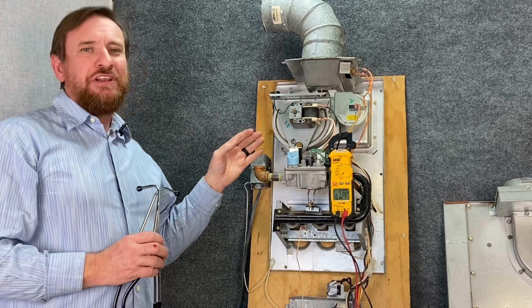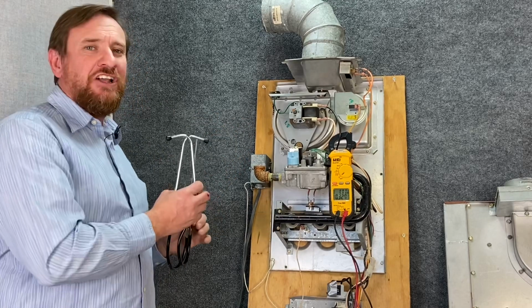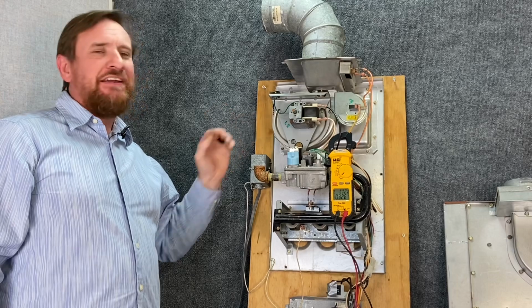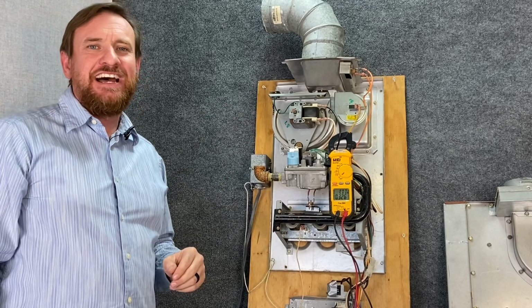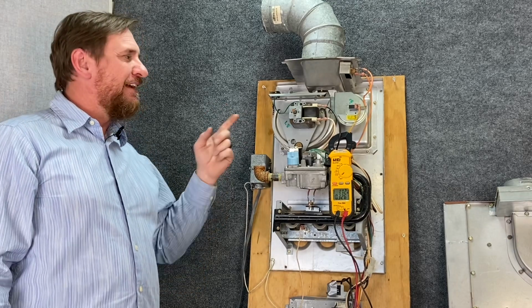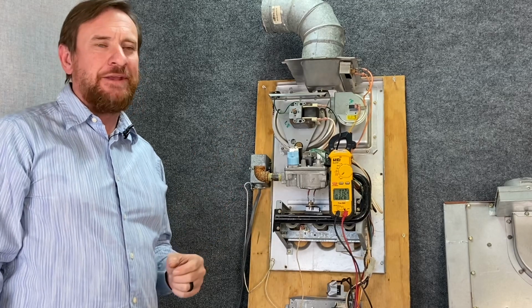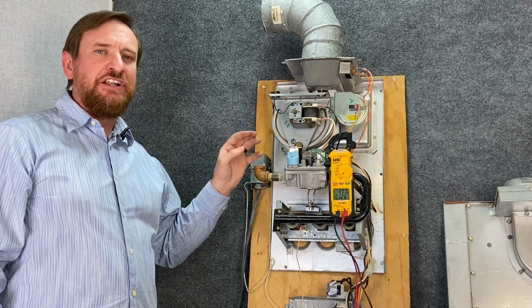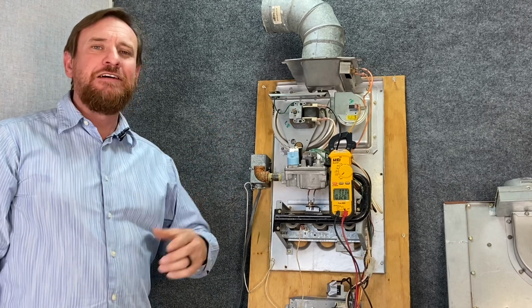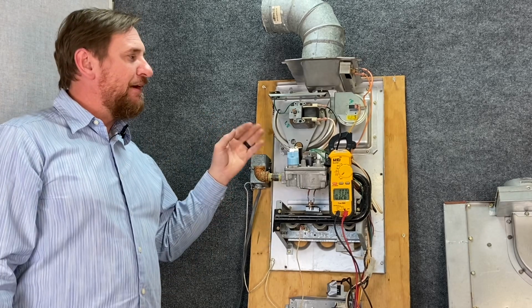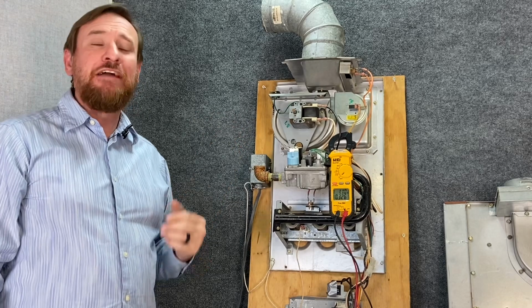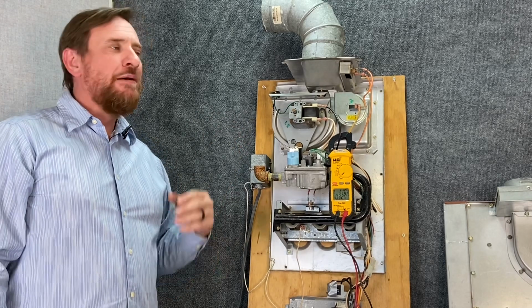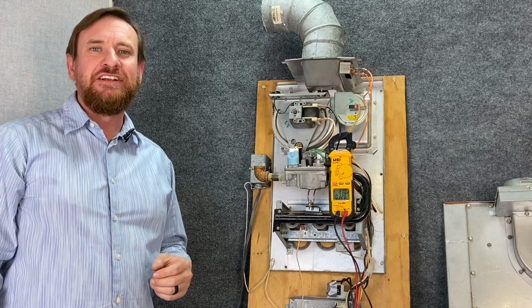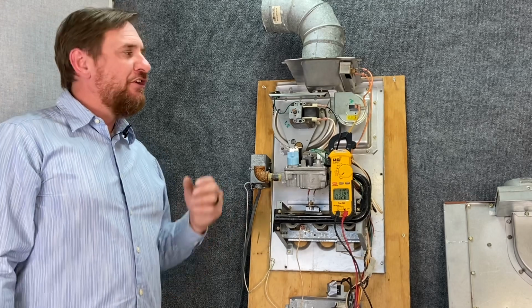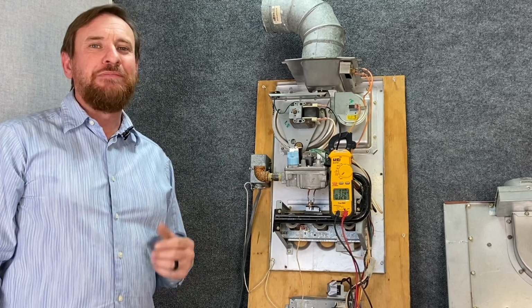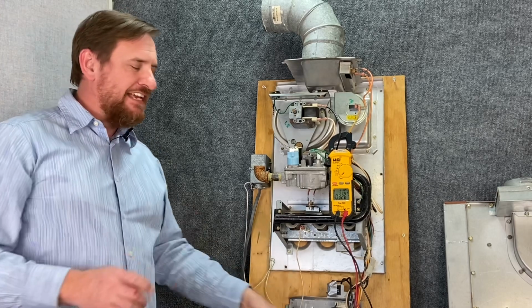Now, the reason I want to go through that extra step, which doesn't take very long, is because I don't want that bearing to fail in the middle of the night, Saturday night, 2 in the morning. I don't want to go back out because I did a maintenance call and I didn't check that bearing. So if I hear that this bearing is starting to go bad ahead of time, I can tell the customer, we've checked the bearings and we're starting to have wear in these bearings. I recommend that we go ahead and replace this now before it becomes an emergency situation later. Now you can do it on both of your schedules instead of having to go out on an emergency call in the middle of the night because she doesn't have any heat. Little things like that can go a long ways.